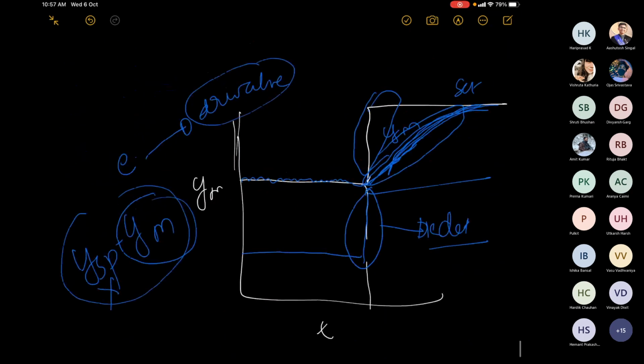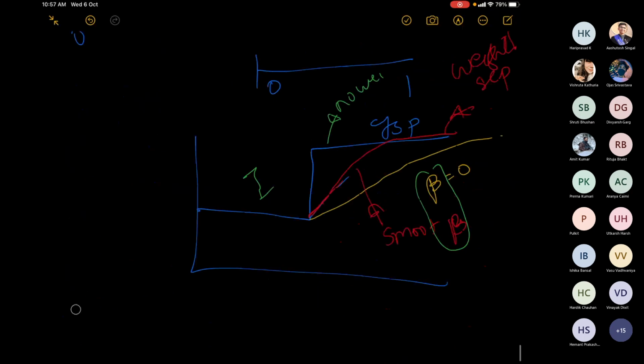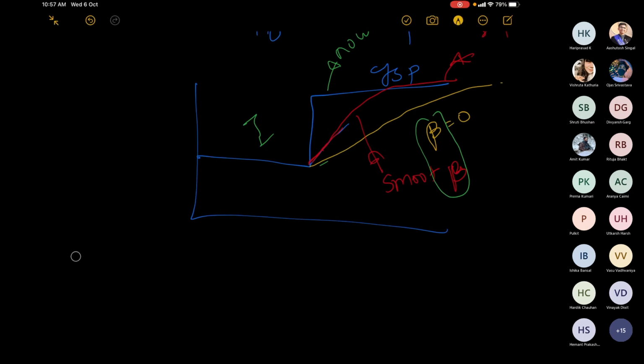When you discard, the overall process becomes very slow. It takes a longer time. And if you don't put beta, it would be a full bump. But if you put a smooth beta, you would see it individually. This is basically the weighted set point, so that you won't bump your controller output directly. Is that okay? Yes, sir.